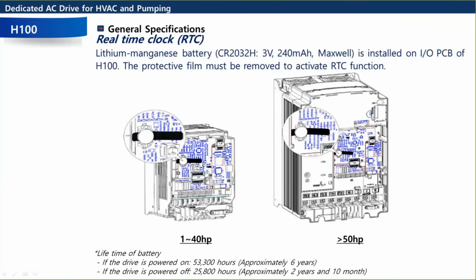We could also set sequence timers once you enable the battery. Oh, and if you look on the bottom here, this is a common question: how long does the battery last? Well, it depends on how often the drive is powered up. Because if the drive is powered up, you're not really using the battery. You're only using the battery when the drive is powered down. So they say about 6 years if you're powered on. And if you're powered off, so if you remove the slip and you leave the drive powered off, or you pull it and it's sitting on the shelf with the battery enabled, you're only going to get about 2 to 3 years. You can buy these batteries anywhere. It's a standard battery. It's not proprietary. And we do have a low battery trip. So if the battery is ever getting low, you're going to get a low warning, so you get a chance to order a battery and then swap it out.